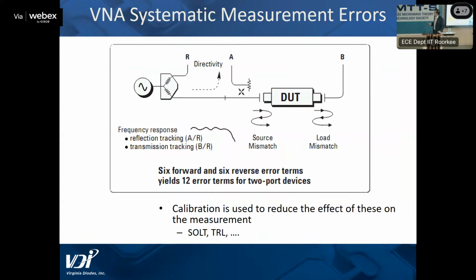As part of the measurement, you need to be able to calibrate out all these other effects of what you're doing, all your couplers and attenuators and mixers and amplifiers. You calibrate, and waveguides need to calibrate all that out. So you're actually measuring at this reference plane here, and it's a very complex set of error terms inside the network analyzer. So you have to do a full calibration of measuring test devices to take out those effects on your measurements.